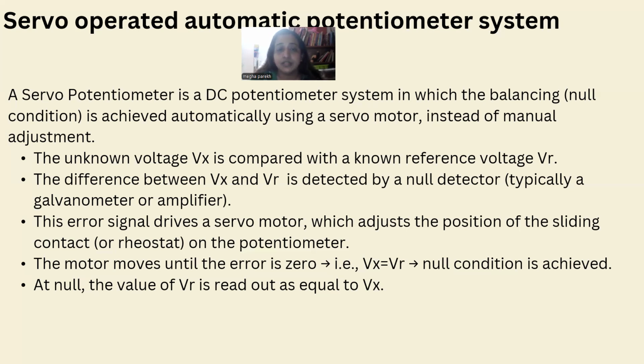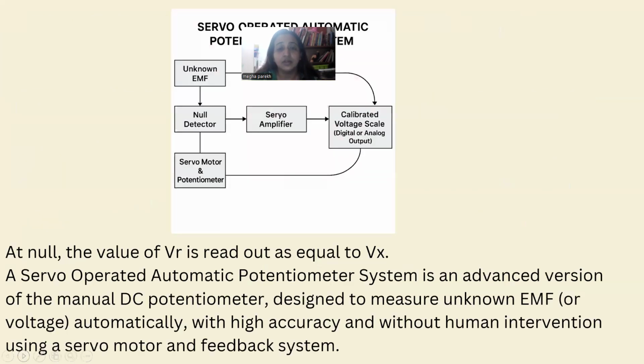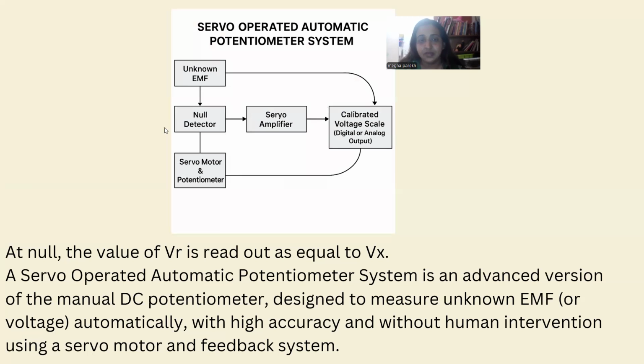The servo potentiometer is a DC potentiometer system in which balancing is achieved automatically using a servo motor instead of manual adjustment. The unknown voltage is compared with the known reference voltage. The difference between Vx and Vr is detected by the null detector. This error signal drives a servo motor to adjust the position of the sliding contact on the potentiometer. So this is a feedback to make the galvanometer zero. The motor moves until the error is zero, where Vx is equal to Vr. Null condition is achieved. At the null, the reference voltage readout equals the voltage to be measured. So we can say this is a servo amplifier and this is the calibrated voltage scale, either analog or digital. And here is a servo motor and potentiometer.